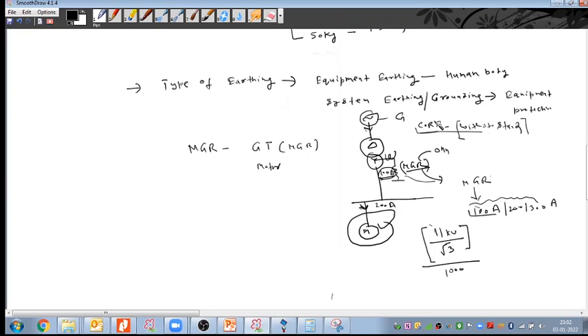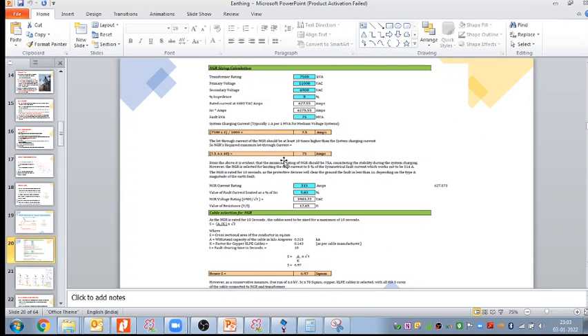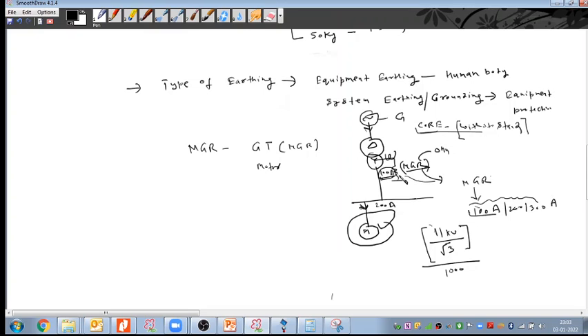So when you talk about the NGR, there are two points we have to see. First, what kind of load current is on that transformer. I hope that on the 5 MVA there might be some rotating machines, the HT motor or MV motor, put on that transformer bus bar. Second, how to calculate the NGR: it does not depend on the transformer rating. It depends on how much current we want to allow to flow. Okay, Srinivasan, clear. Don't worry, in the next class I will start from the NGR calculations again. The values are the same as what we discussed today. We will only convert them into a systematic pattern.